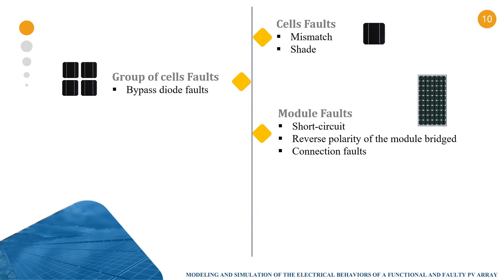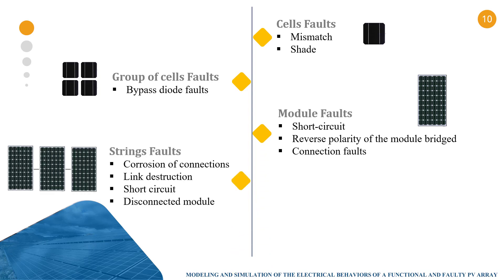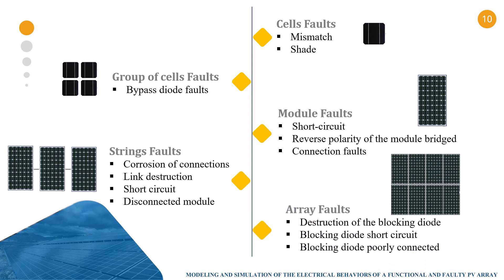In modules, we can have short circuit, reverse polarity or connection faults. In a string, we can have corrosion of connection, link destruction, short circuit or disconnected module. In an array, we can have destruction of the blocking diode, short circuit or blocking diode poorly connected.